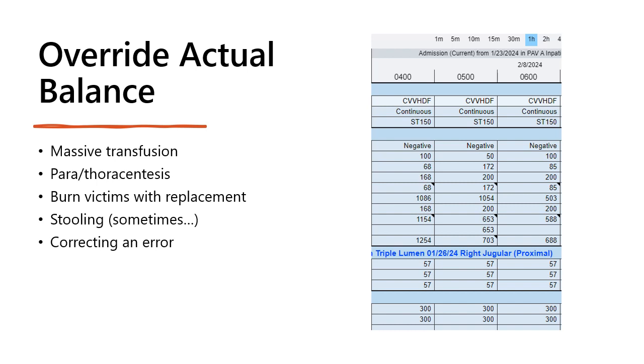There's any number of different errors that you could encounter that you could fix, but in the patient whose flow sheet is what I would call hopelessly broken, this is also a way to reset it to something more realistic. So for example, if the patient's suggestion was to pull 4,800 milliliters next hour, one might look at their overall I's and O's balance for the last couple days on CRRT and come up with a more realistic number. Sometimes that must be done with the discretion of the nephrologist if it's going to be a big change.